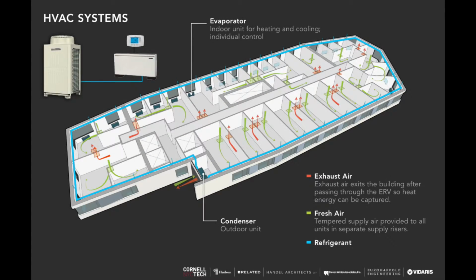The big difference between conventional HVAC equipment and this equipment is that rather than pushing water around the building, which is sort of like a water source heat pump, or having the vapor compression cycle happen within a single box, these units push refrigerant around the building, and it splits the vapor compression cycle between the indoor units, which we call evaporators, and the outdoor units, which we call condensers. We've zoned the system in this building. This is not exactly how it's going to be, but diagrammatically indicative of the fact that we have a north loop and a south loop.